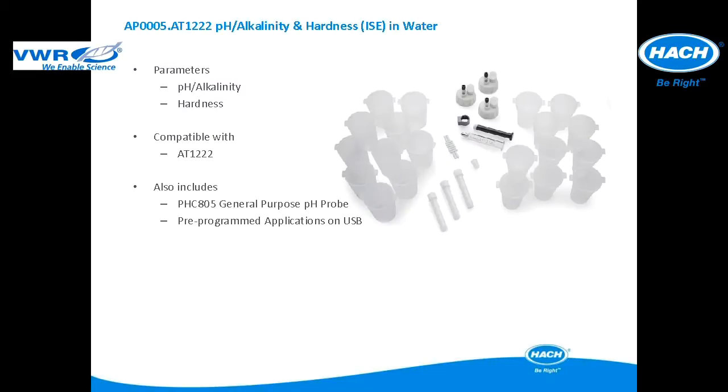This application package is used for pH, alkalinity, and hardness in water applications. The application package is compatible with the AT1222. It includes all of the items pictured and a PHC805 general purpose refillable pH electrode. The pre-programmed applications are included in a USB application key.